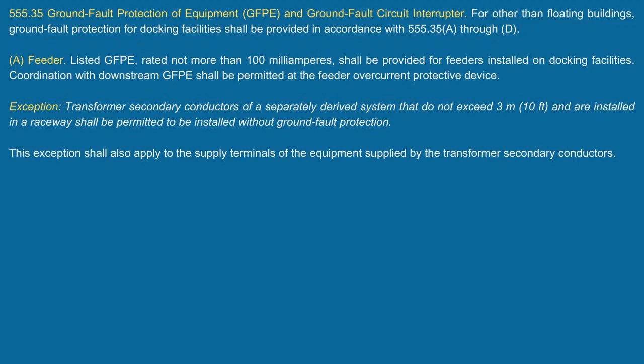He's making a blanket statement that anywhere that you just pick up current, that's an outlet. That's not correct. And I've been saying this over and over, and this particular section here that we're dealing with, that deals with the ground fault protection of equipment and GFCI for personnel protection, they've got them separated here, and they're specifically calling out receptacles. And the reason they are, because a receptacle is a device where it's receiving its current, but the receptacle outlet is the box. That's where the outlet is, okay? It's not the receptacle, it's the outlet box, and that's where your cord and plug connected.